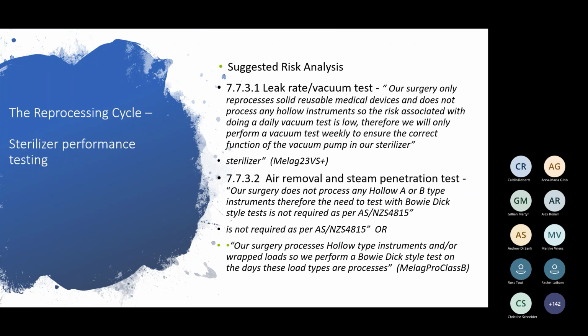So 7.7.3.1, the leak rate vacuum test. Our surgery only reprocesses solid reusable medical devices and does not process any hollow instruments. So the risk associated with doing a daily vacuum test is low. Therefore, we will only perform a vacuum test weekly to ensure the correct functioning of the vacuum pump in our sterilizer. And that could be a risk analysis for a MELAG 23VS.